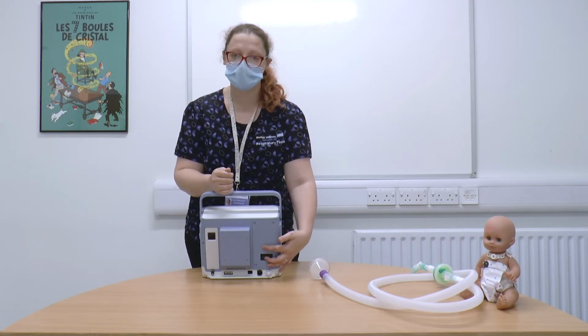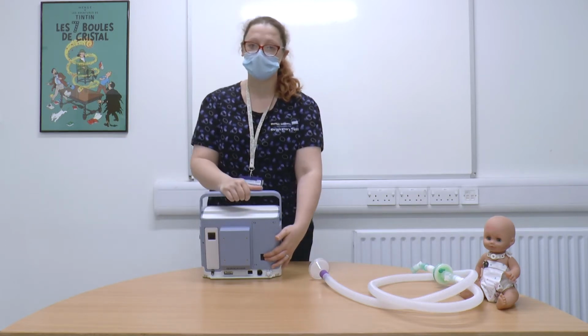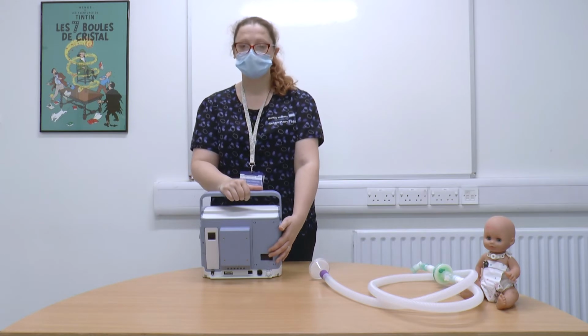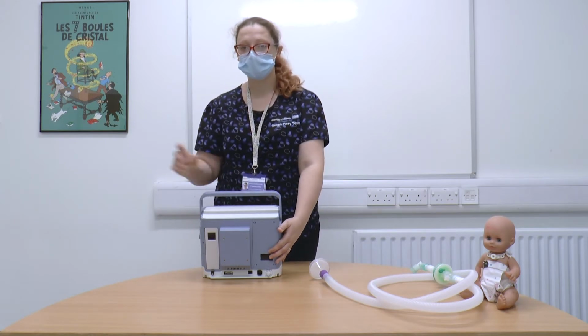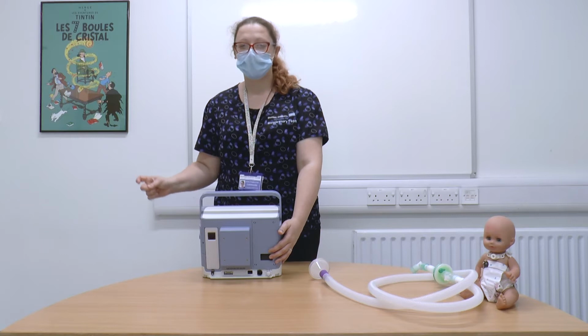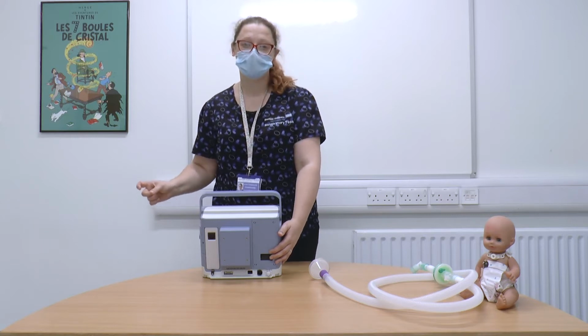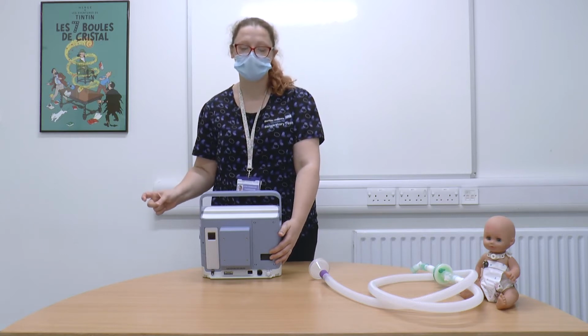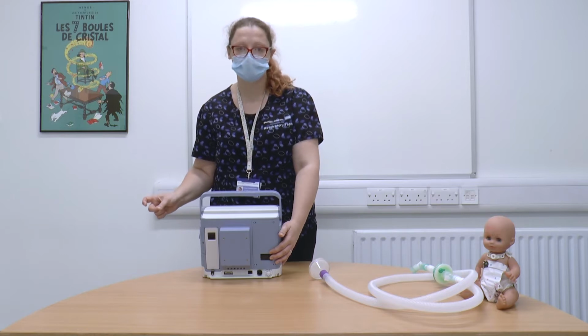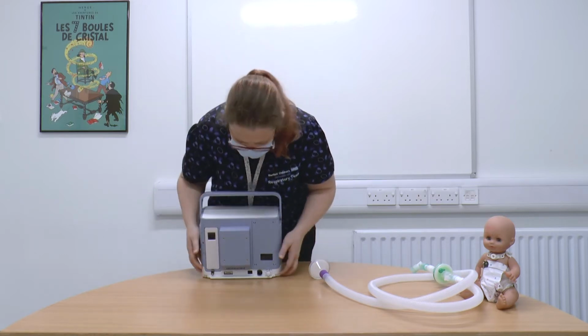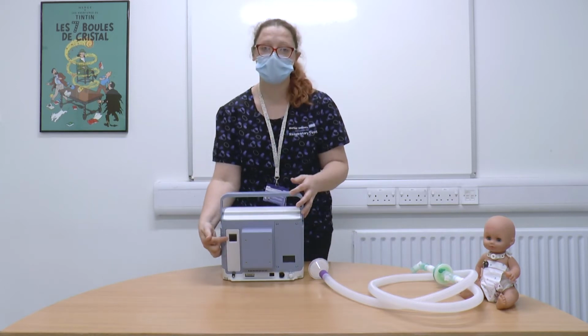Because it's coming in where the air is coming in, it will not affect the flow of the ventilator. Same as for a Trilogy, if you are using an oxygen port at the output flow, it will not know whether the air is coming from the child or from an oxygen machine, so it will affect the flow of pressure being delivered. You have got also the external battery.